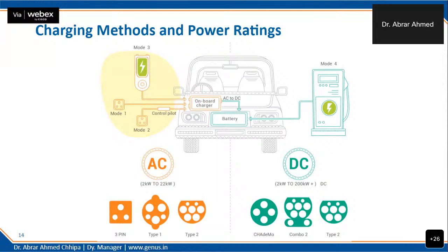Looking at the diagram, modes 1 and 2 are applicable for connecting an EV to the standard socket outlet available at home, using a cable and plug. Mode 1 is also known as dumb charging and permits no communication between the EV and EVSE, and its use is not recommended.